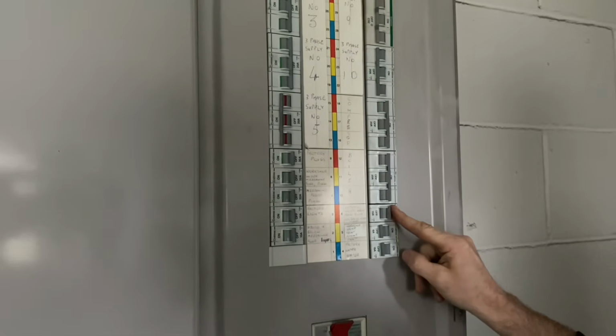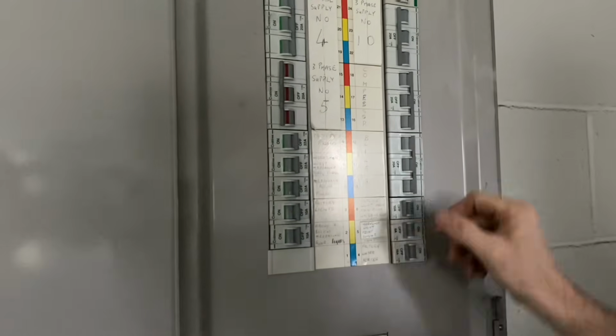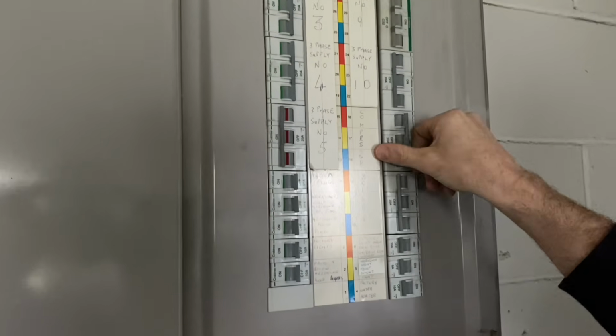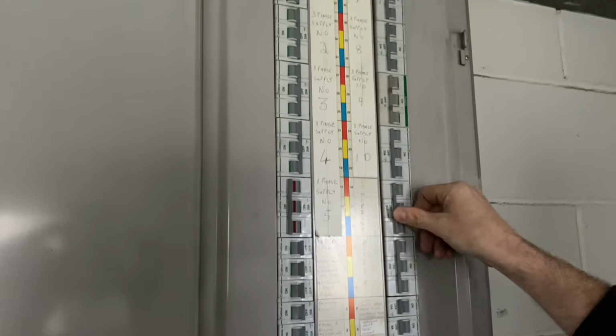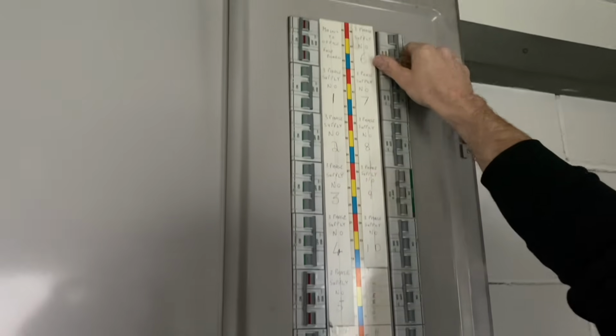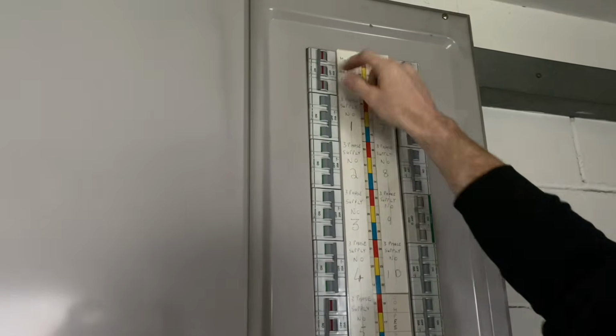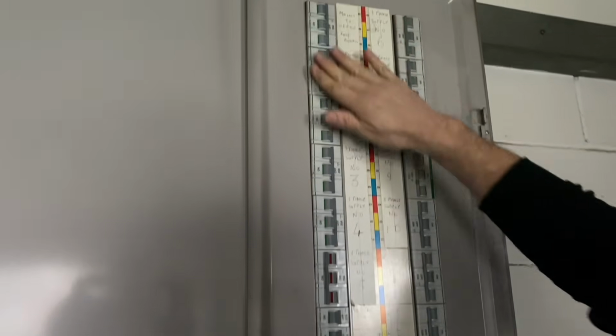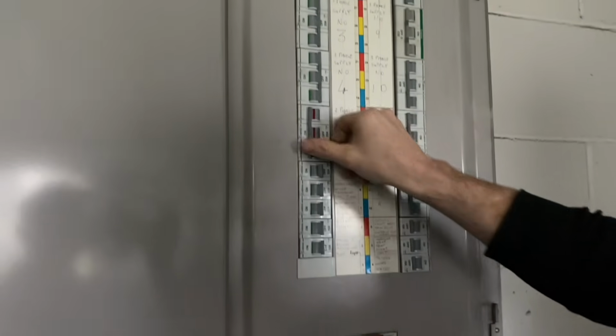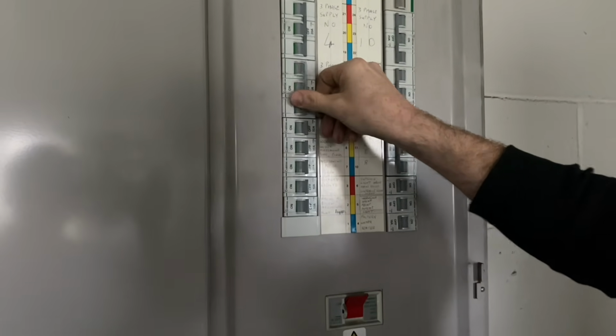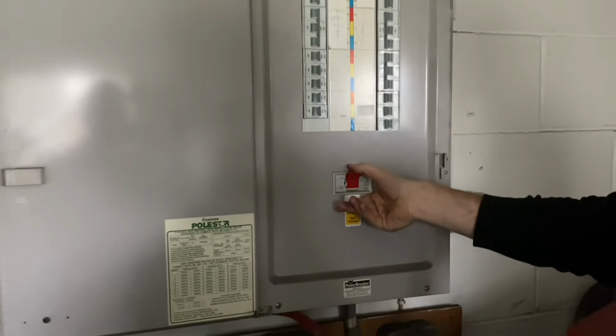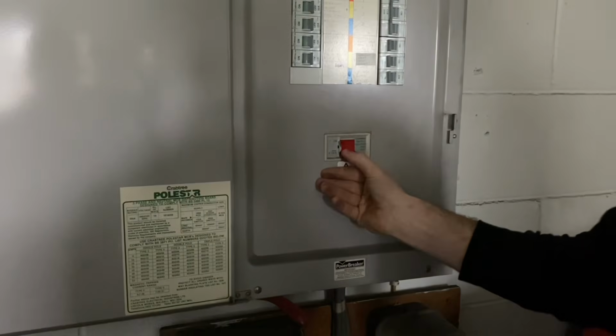Do you want them to stay on just for now? No, we'll turn everything off. We'll do it properly. And then we've got our three-phase breakers. So that's a blower, a compressor, and a three-phase supply to another board there, the office board. We've turned off a lot of the local loads as well, so we haven't got loads of stuff on full load for the breakers. And so that looks like all the loads have been taken off. Yeah, and we're going to do the main switch now. So now it's quite happy just to turn the main switch off.